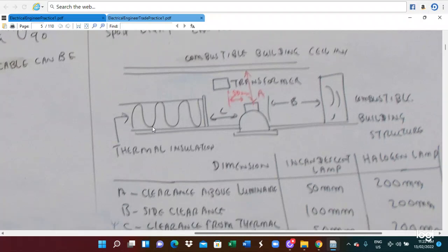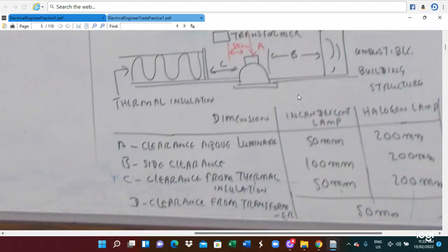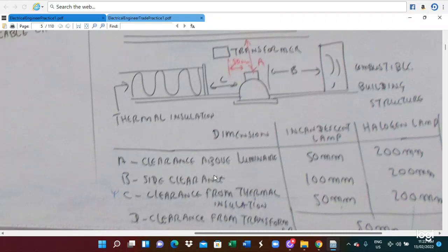This is for when you use thermal insulation, and also when you use any transformer. So, above ABCD: A is clearance above the luminaire. In this case, incandescent light is 50 millimeter, halogen light is 200 millimeter. B is side clearance. Side clearance is 100 for incandescent, and 200 millimeter for halogen light.